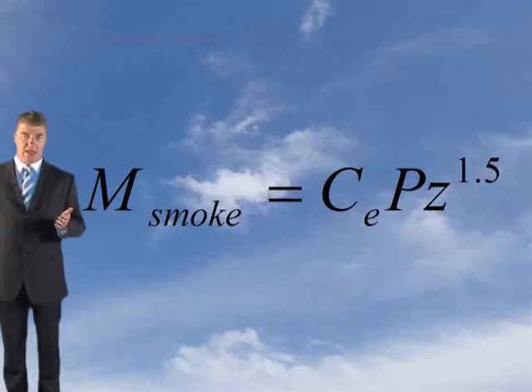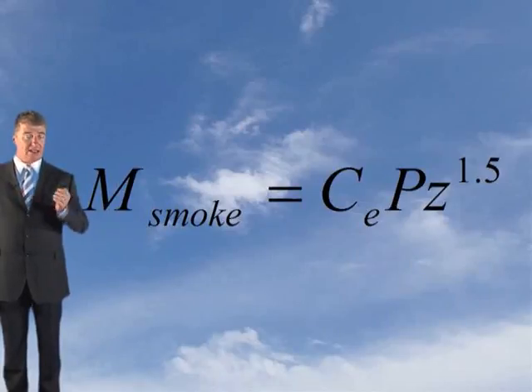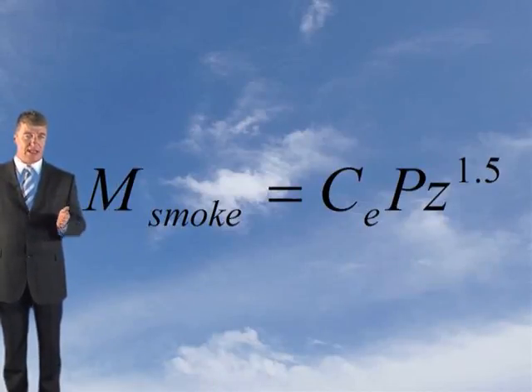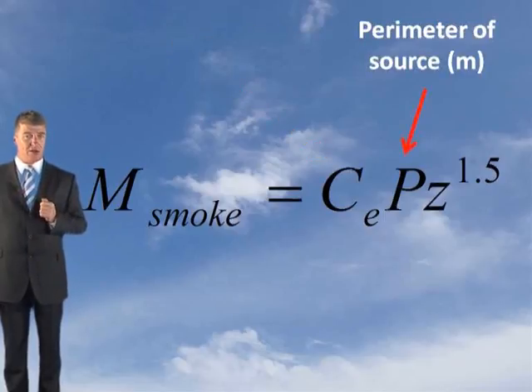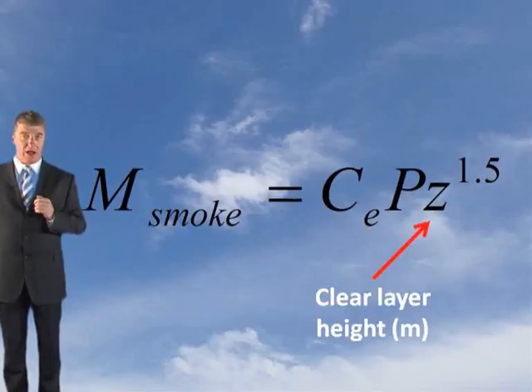Here is the model available for the near field axisymmetric plume: M_smoke equals C_E, which is the coefficient of entrainment, times P, which is the perimeter of the source, times Z to the power of 1.5, which is the clear layer height. To apply this model, you need to determine which coefficient to apply.